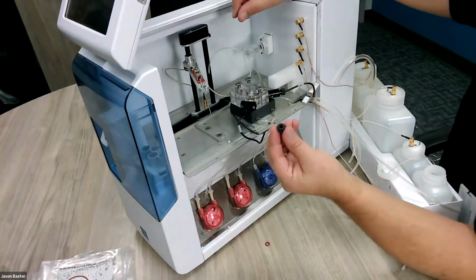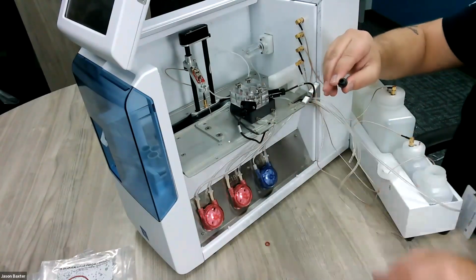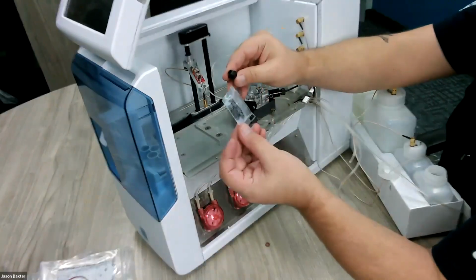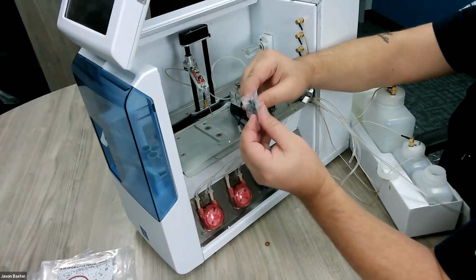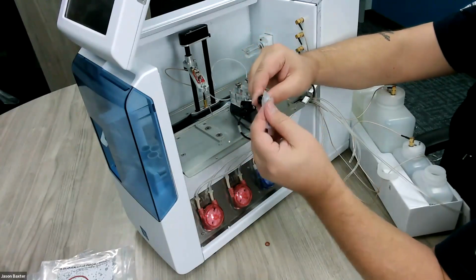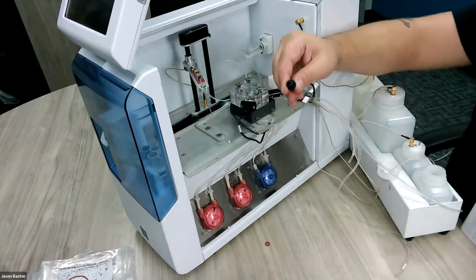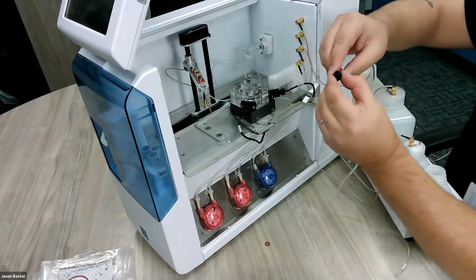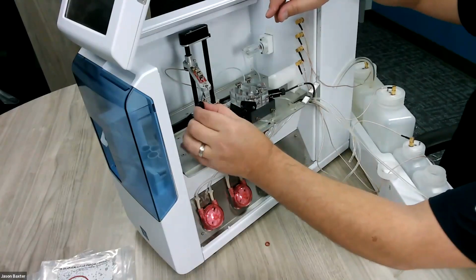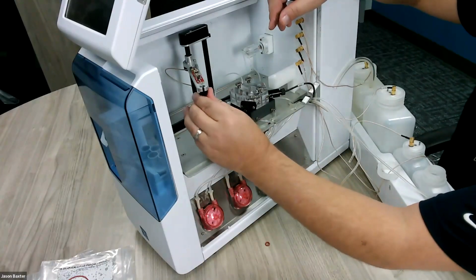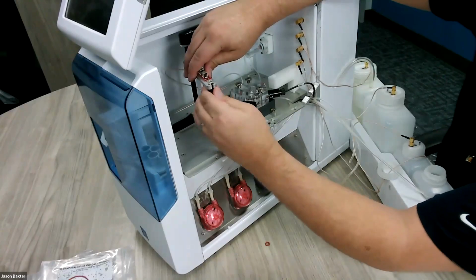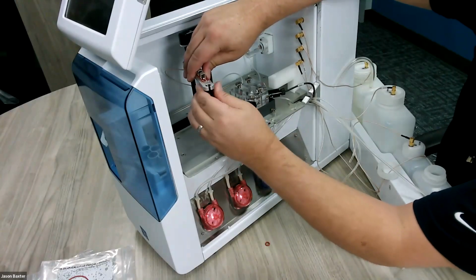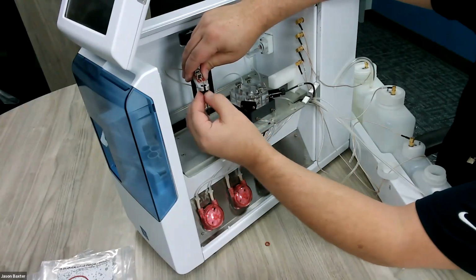If you encountered this black cone that was very difficult to remove, again, get the last little residual part of your silicone grease, apply some silicone grease to these threads. You don't need a lot. Wipe your hands off when you're done. Put this back up in and reinstall. Again, finger tight is all you need. You don't have to go crazy. You don't need pliers or vice grips or anything like this to tighten this up.